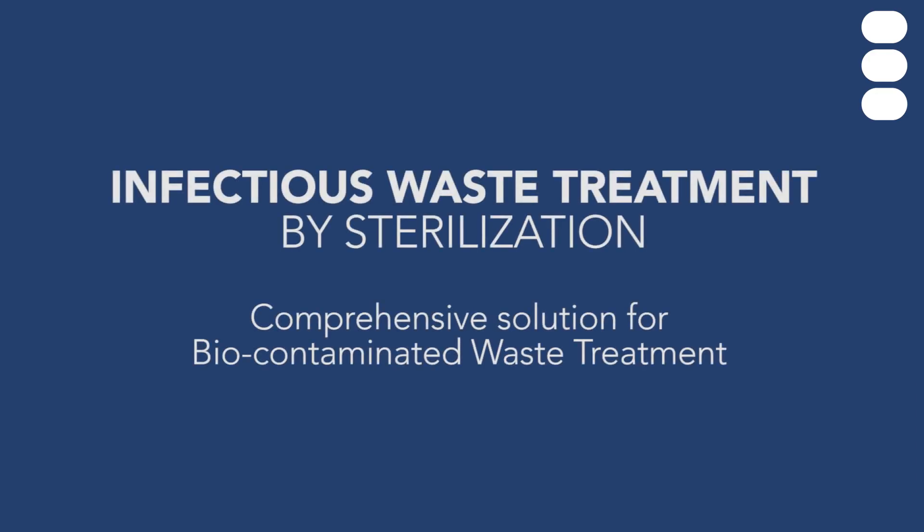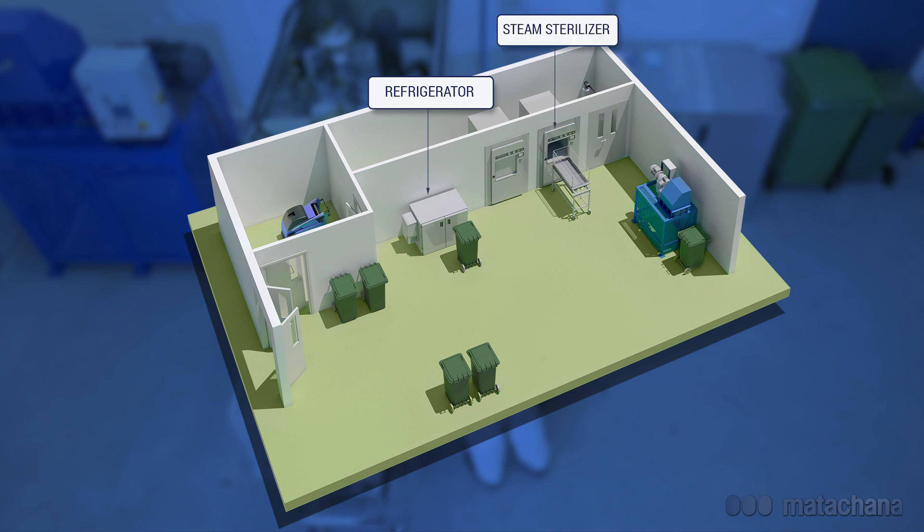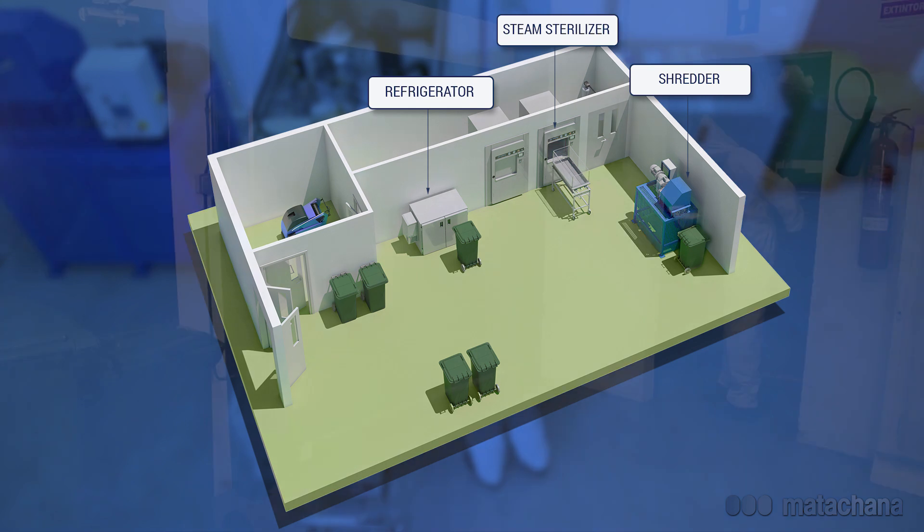Infectious waste treatment by sterilisation. Comprehensive solution for biocontaminated waste treatment. In order to provide a solution to the waste management problem at hospitals, the company Matachana has developed a solution which consists of a refrigerator to prevent waste from fermentation, a steam steriliser to convert the biocontaminated waste into urban waste, and a shredder to reduce the final volume, making the waste unrecognisable.